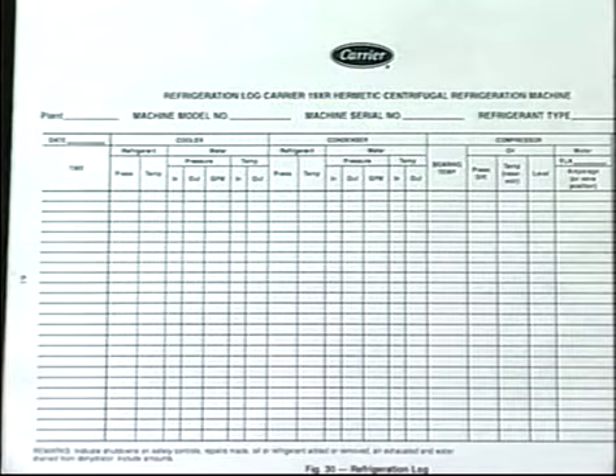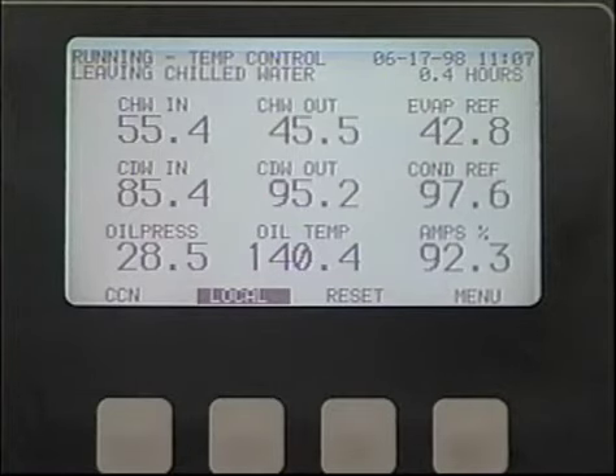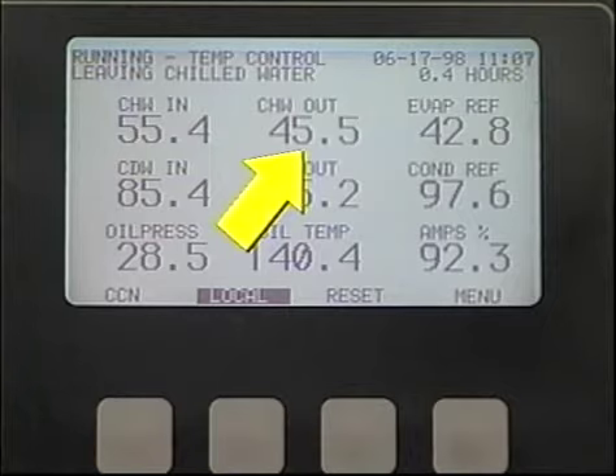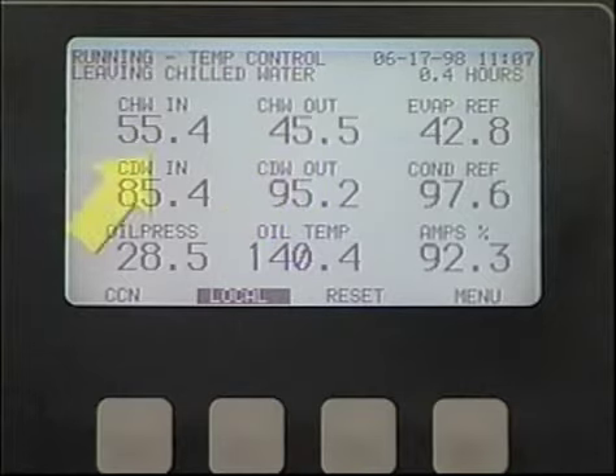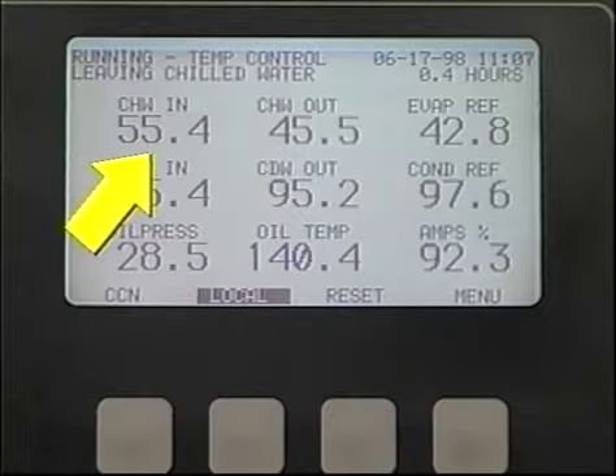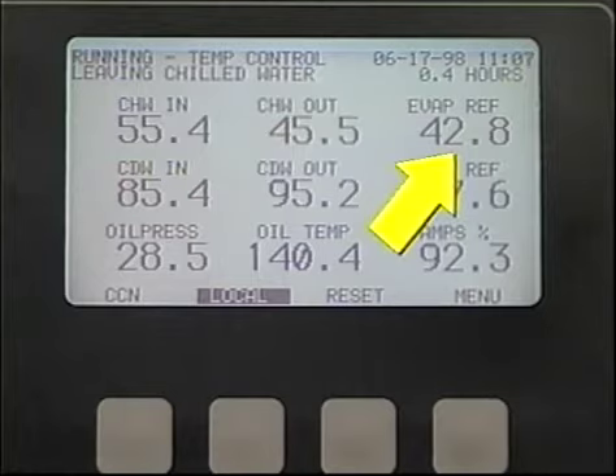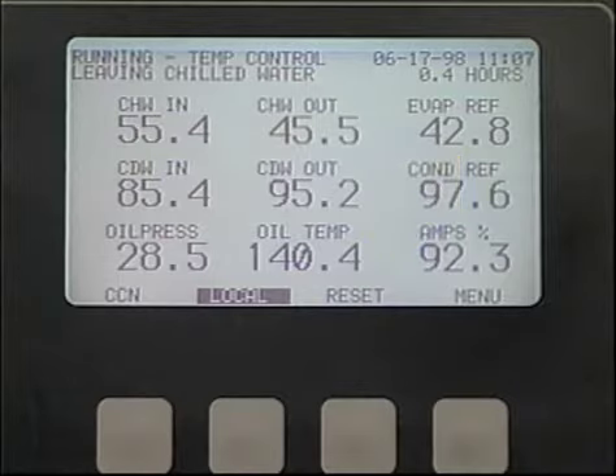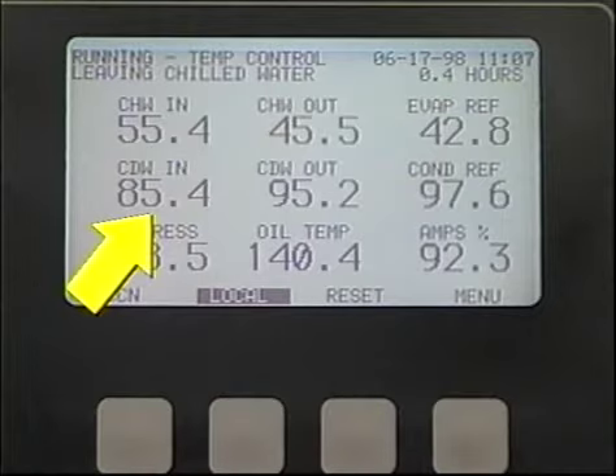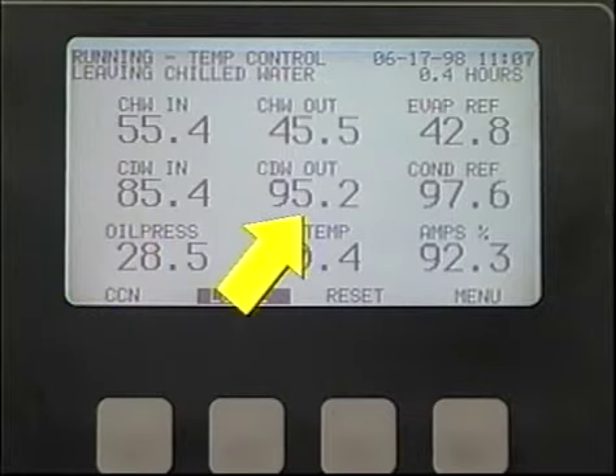Be sure to always indicate on the log sheet any service or maintenance performed, including quantities of any oil or refrigerant added or removed. Here are some typical temperature and pressure ranges for a typical comfort cooling application. The chilled water leaving the cooler should be close to the chilled water set point, and the return water should be about 10 degrees above the leaving water temperature at full load conditions. The saturated temperature of the refrigerant in the cooler will vary with design conditions, but will be typically 34 to 45 degrees Fahrenheit. Condenser cooling water is normally in a cooling tower circuit and will typically enter the condenser around 85 degrees Fahrenheit and leave at about 95 degrees Fahrenheit at full load conditions.